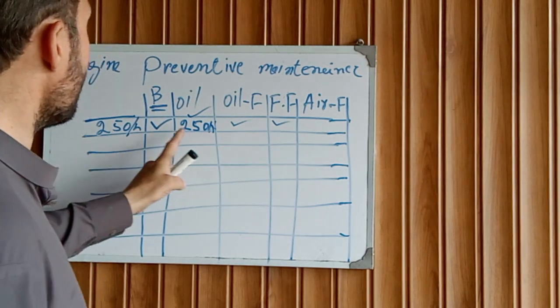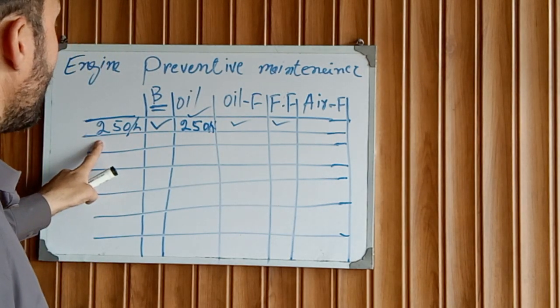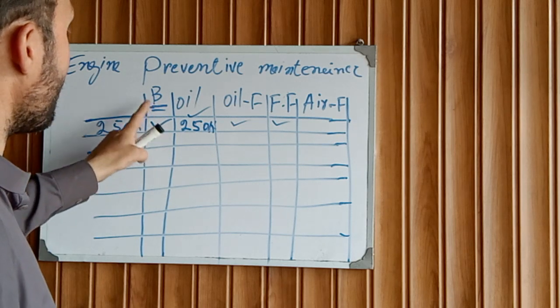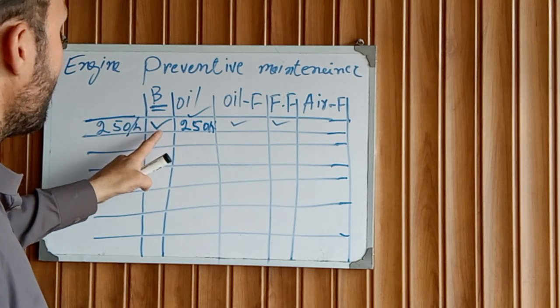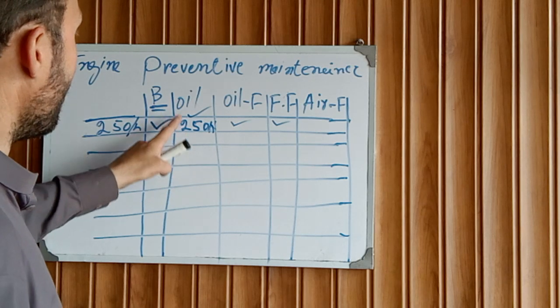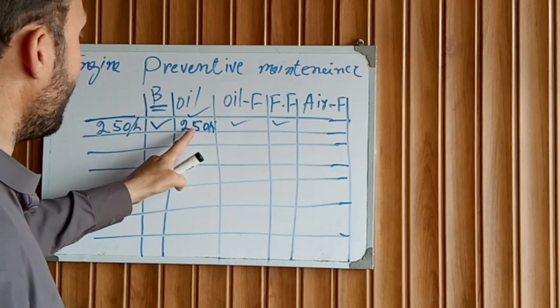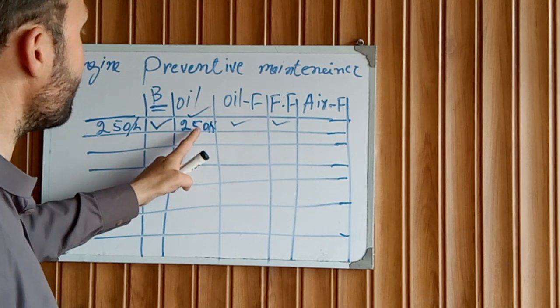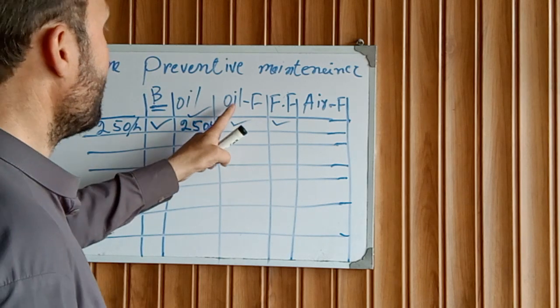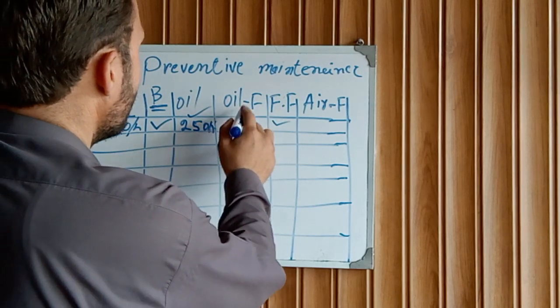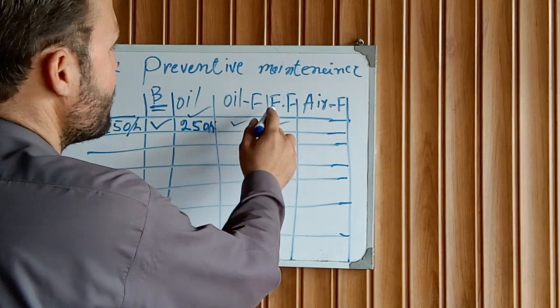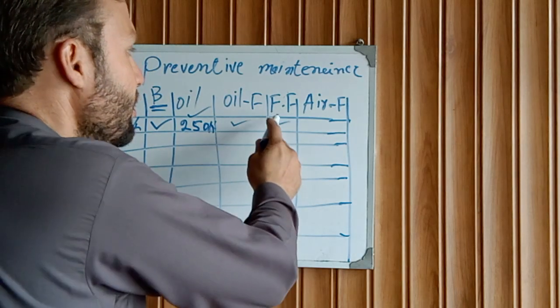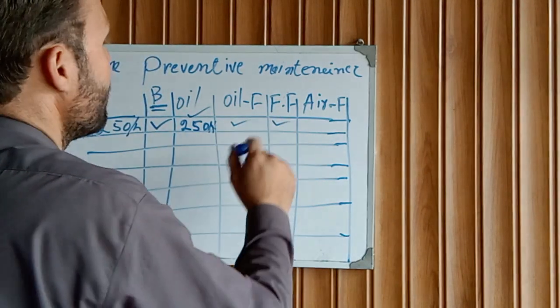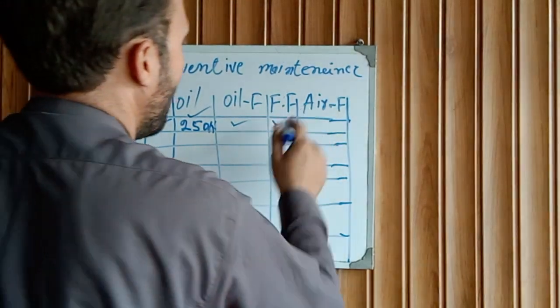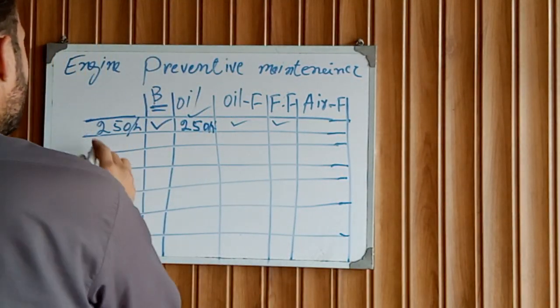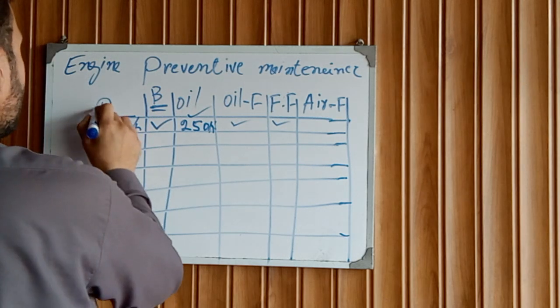All this needs to change at 250 hours: check the battery acid, clean the battery, the battery posts, distilled water, and change the engine oil at 250 hours running. Change your oil filter along with the oil change, and change your fuel filter as well - oil filter and air filter are required.